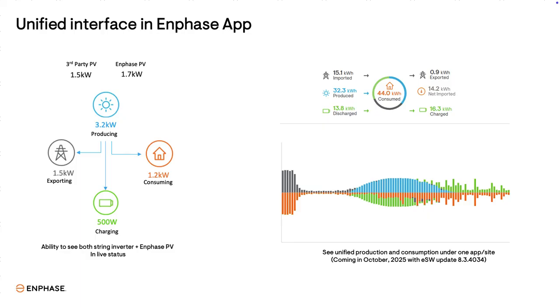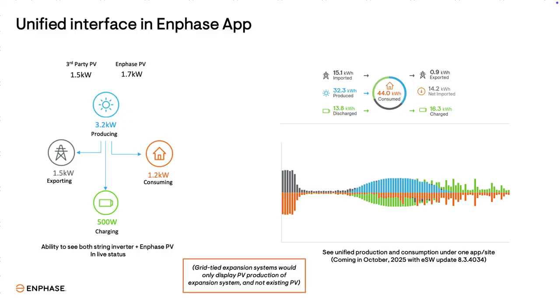Homeowners with Enphase expansion systems will have a unified interface in the Enphase app, which displays combined solar production of the existing PV and the expansion PV system. The exception would be for grid-tied systems, since the consumption and existing PV are measured by parallel CTs — the IQ Combiner 6C can't monitor the existing PV.